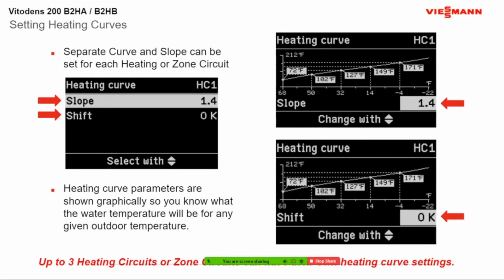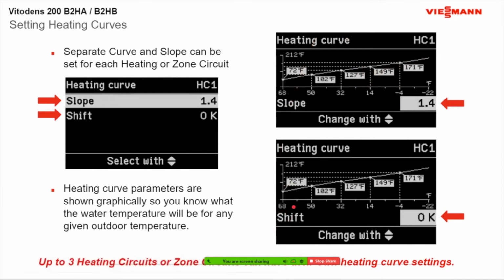Shift is a little different. As you can see, it says okay. So when I used to ask people what their shift was, they would say it's okay, including myself. But what that okay actually really stands for is 0 Kelvin. So it's a temperature. So that's doing the bottom end of your scale. Remember with our room temperature set point, if you have it set at 68 degrees, our warm weather shutdown would be 70 degrees outside.